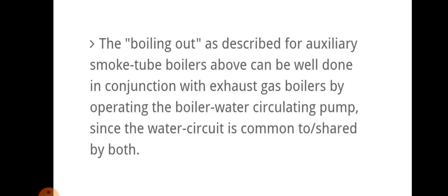The boiling out, as described for the smoke tube boiler above, can be well done in conjunction with the exhaust gas boiler by operating the boiler water circulating pump, since the water circuit is common to both. Thank you, this is the maintenance that we have done on the exhaust gas boiler.